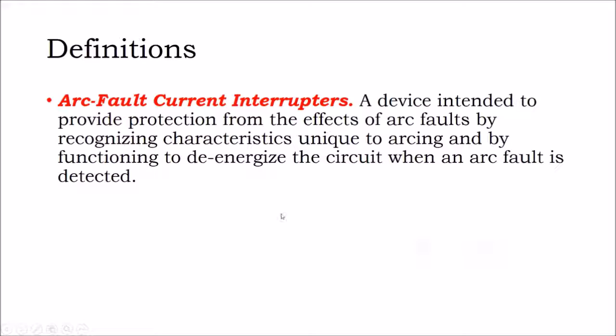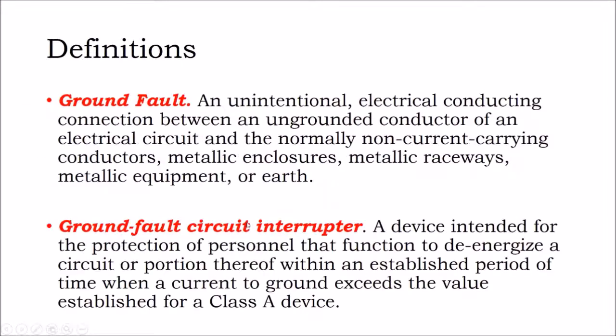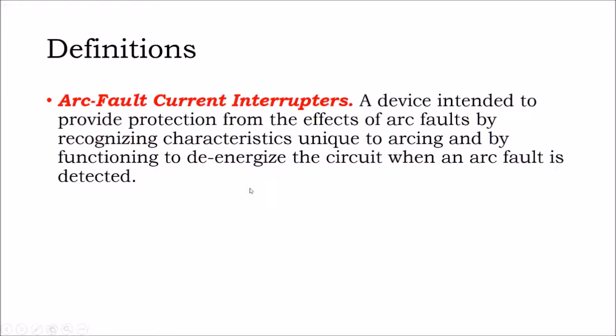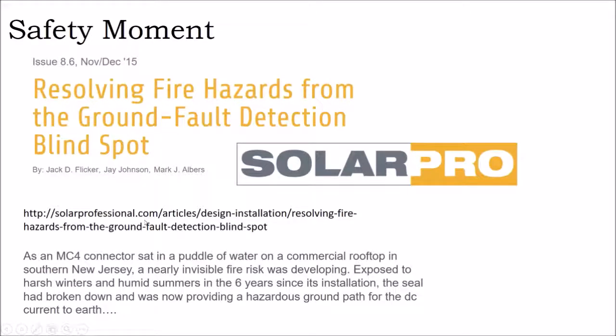And so the National Electric Code over time, it used to be that it just required ground fault protection and ground fault circuit interrupters. Nowadays, the inverters have arc fault detection in them as well. And that's produced a phenomenon where owners of older systems think that solar arrays are bulletproof and nothing ever goes wrong with them, whereas when you install a newer inverter with arc fault detection, it recognizes when that MC4 connector is not made up correctly but still operational, and it shuts off. So that's for the best, but it's also showing you that older legacy components eventually should be upgraded to the latest iteration of code.